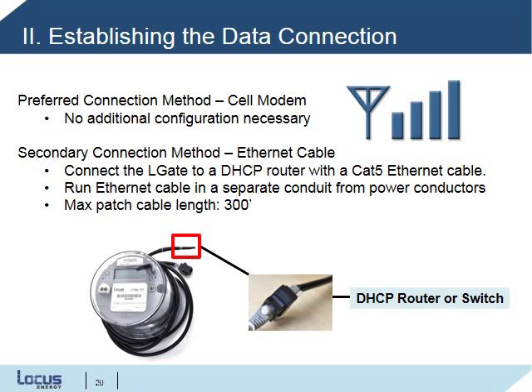If a cell connection isn't possible, perhaps you're in an area with weak cell reception, a secondary method is Ethernet cable. To set this up, connect the LGate to a DHCP router with a Cat5 Ethernet cable. Always run this Ethernet cable in separate conduit from power conductors, and keep the length of this cable to 300 feet or less. Some additional configuration is required for the secondary connection method with Ethernet cable.